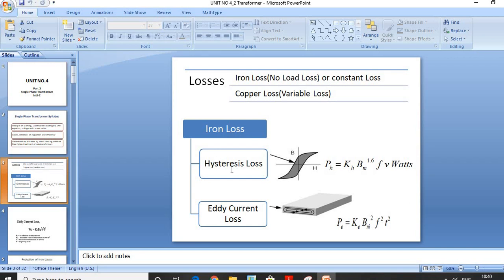There are two types of losses that take place in the Core: Hysteresis Loss and Eddy Current Loss. The Transformer works on AC supply, so an Alternating Flux is produced. When this Alternating Flux conducts from Primary Winding to Secondary Winding through the Core, it creates a Reversal of Magnetization in the Transformer Core, which creates a loss called Hysteresis Loss.